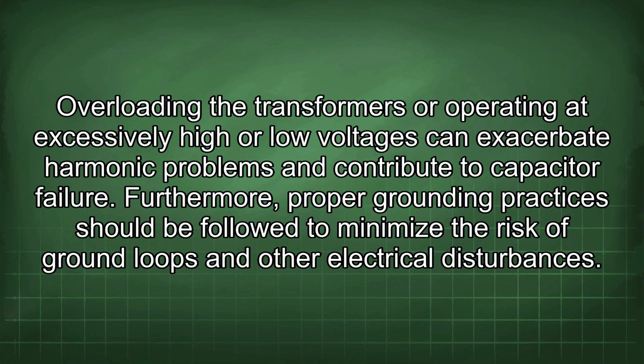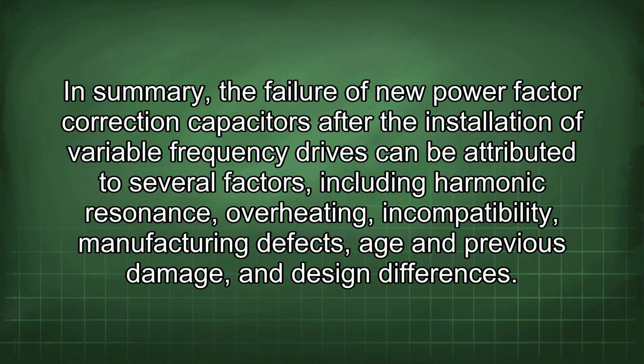Furthermore, proper grounding practices should be followed to minimize the risk of ground loops and other electrical disturbances. In summary, the failure of new power factor correction capacitors after the installation of variable frequency drives can be attributed to several factors, including harmonic resonance, overheating, incompatibility, manufacturing defects, age and previous damage, and design differences.